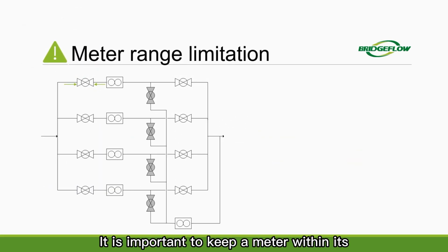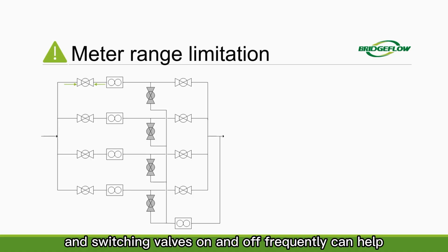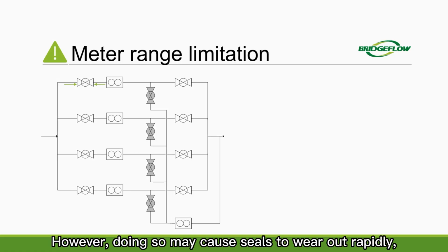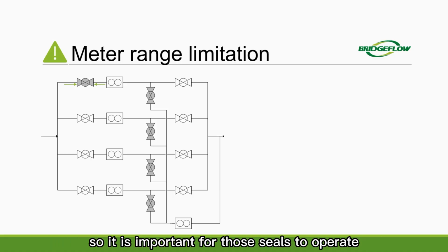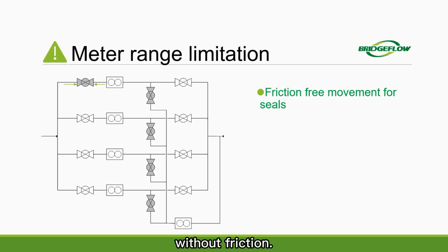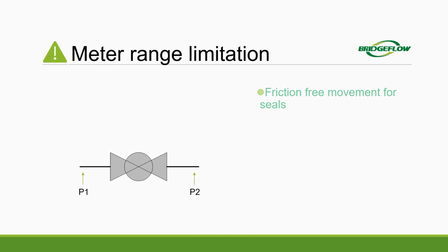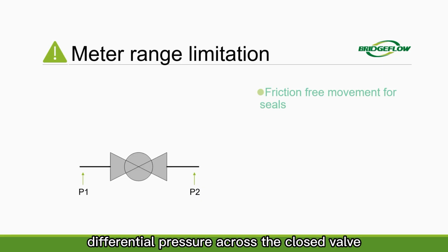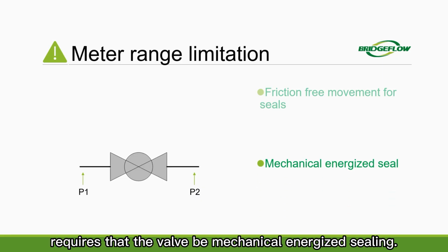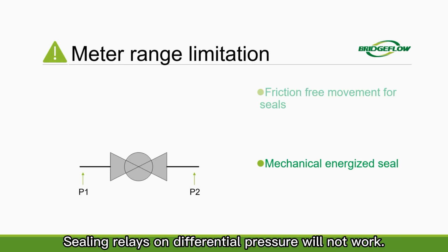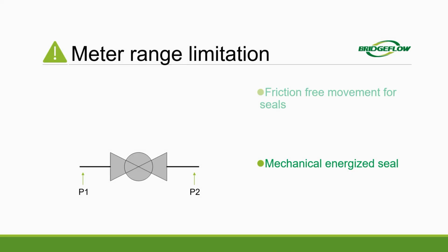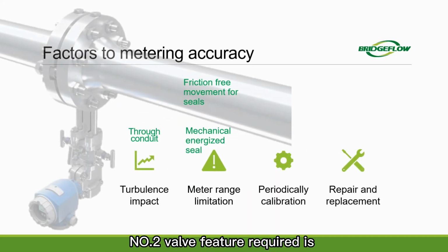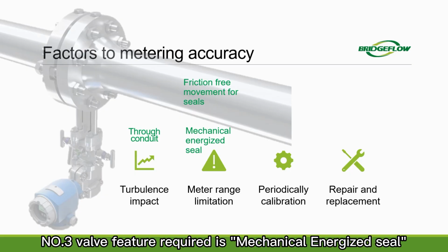It is important to keep a meter within its range of operation. Connecting meters in parallel and switching valves on and off frequently can help to accomplish this. However, doing so may cause seals to wear out rapidly, so it is important for those seals to operate without friction. Additionally, the low differential pressure across the closed valve requires that the valve be mechanical energized sealing. Sealing relying on differential pressure will not work. Number 2. Valve feature required is friction-free movement for seals. Number 3. Valve feature required is mechanical energized seal.